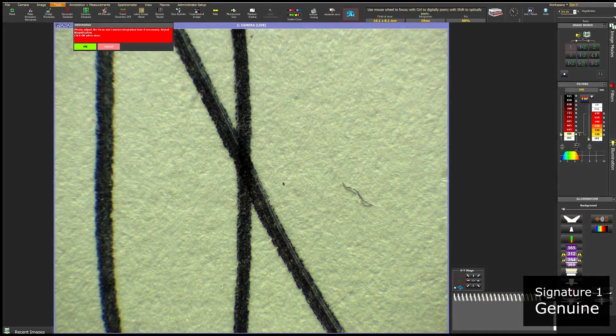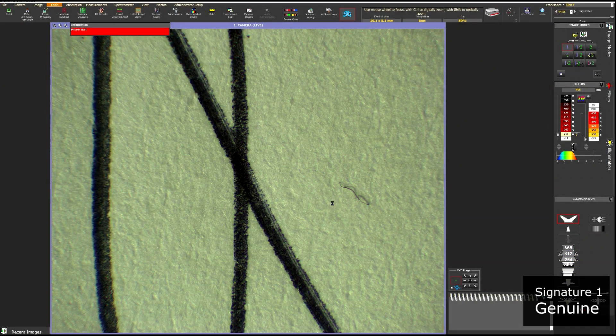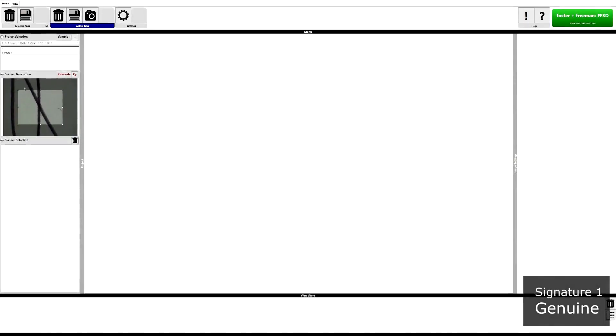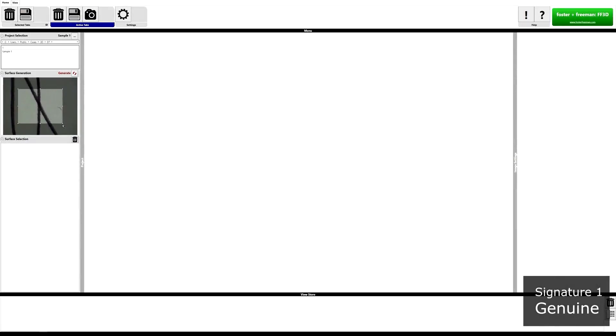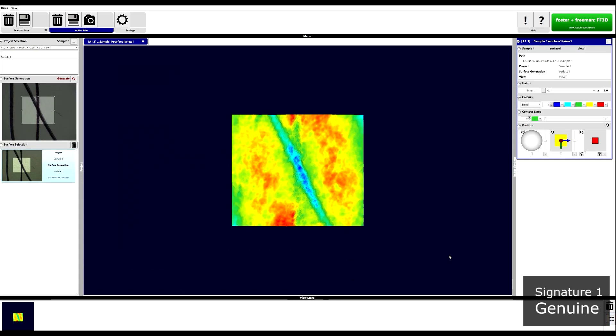It is usually advised to use a higher magnification to get the most clear results possible. As instructed, we will check the focus and then click OK. We will give this a name. The VSE will then take a series of images under different lighting angles, and then the 3D imaging software will automatically open. Here we need to select the desired area to process. In the majority of cases, it won't be necessary to select the entire image, so to increase the speed of the final results, we will just select the small point here and then click Generate.